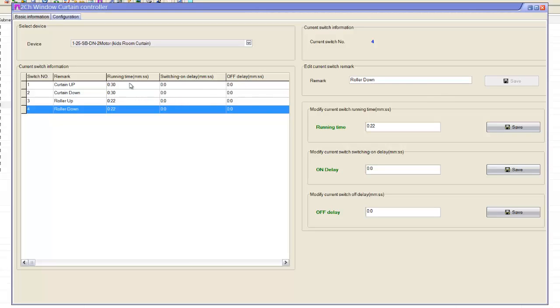So here we can see that there are some small configurations here. There is a running time, switch-on delay, off delay. The running times, you always calculate how long your curtain motors take to go up and take to go down. So normally we calculate that based on the time.